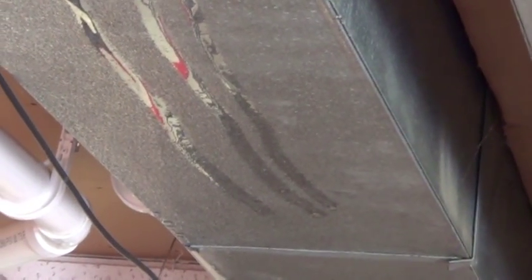So as you look at the ducts here, I don't know if you can see, we've got condensation all the way through. I don't know if you see the streaks on the ductwork, but I've got water on my fingers on this. So basically there's two things going on here. Number one, we've got leaky ducts and we need to make sure that they're sealed for the home. Number two, the ducts are not insulated. We're in a garage. It is humid in the garage. And we have the air conditioner running, and that's about 55-degree air running through this ductwork. As you can imagine, ducts get pretty cold with that air. So that cold surface and humidity causes condensation to form.